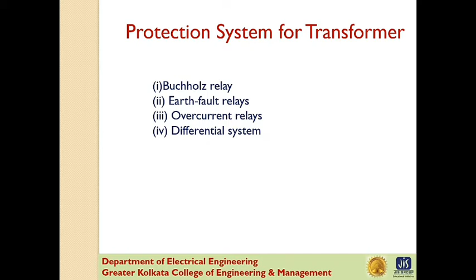Buchholz relay. Buchholz relay is a gas-actuated relay installed in oil-immersed transformer for protection against all kinds of faults. Named after its inventor Buchholz, it is used to give an alarm in case of incipient, that is slow developing, faults in the transformer, and to disconnect the transformer from the supply in the event of severe internal faults. It is usually installed in the pipe connecting the conservator to the main tank. It is a universal practice to use Buchholz relay on oil immersed transformers having rating in excess of 750 kVA.